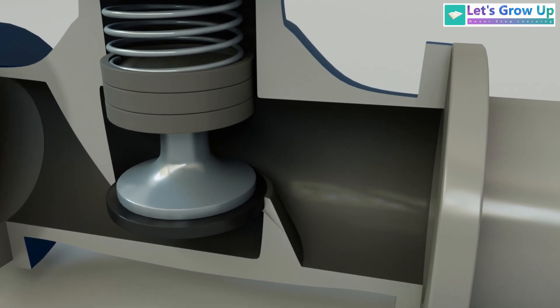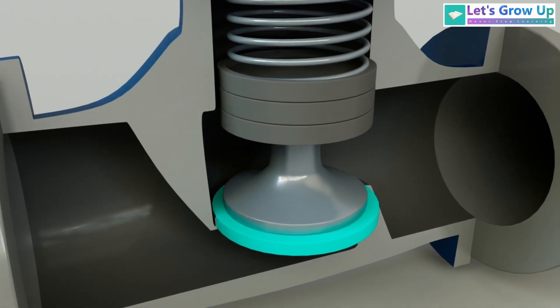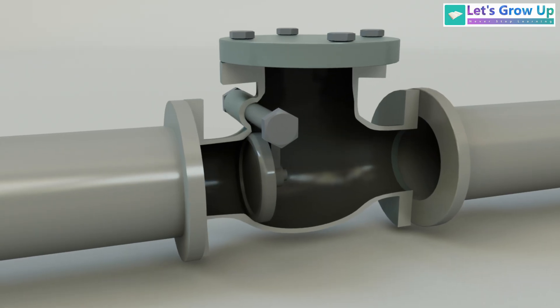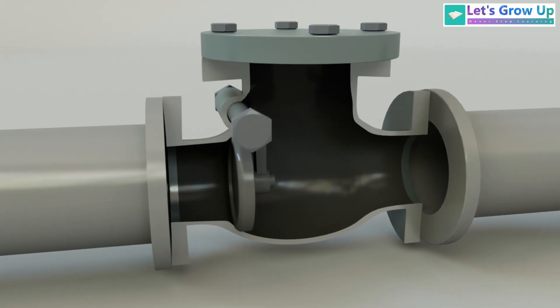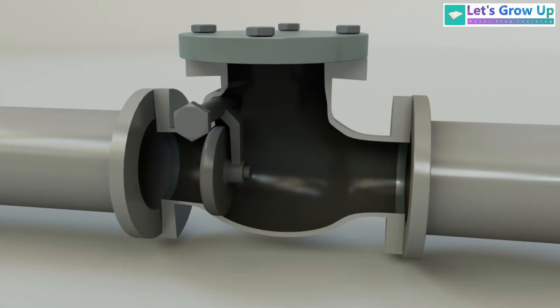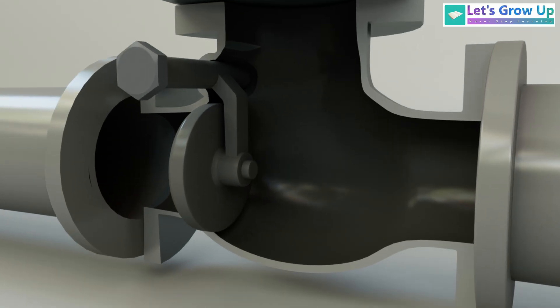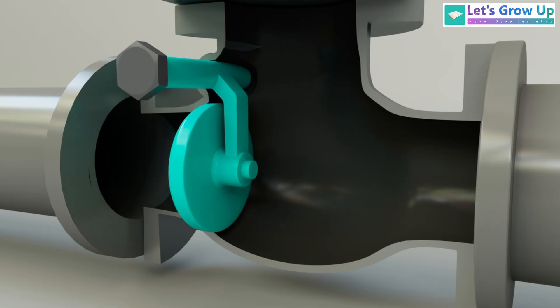This is a swing type non-return valve. The swing type valve is one of the most common and versatile NRVs that you will encounter. It is known for its simplicity and minimal pressure drop. A swing valve features a hinged disc, similar to a door, that hangs from a pivot point within the valve body.